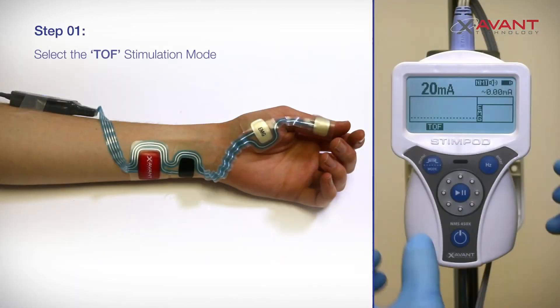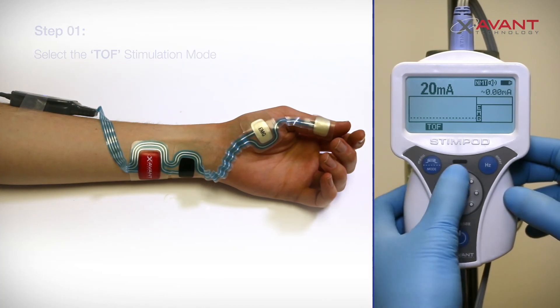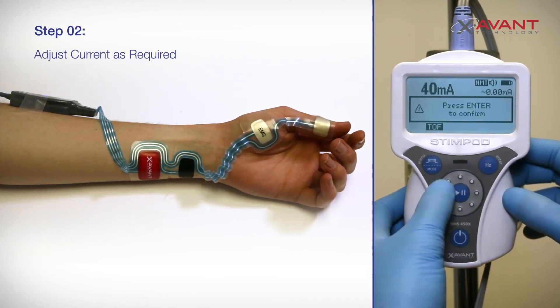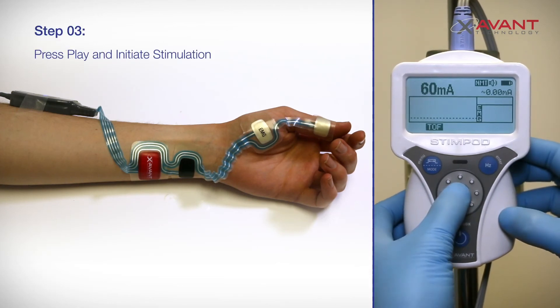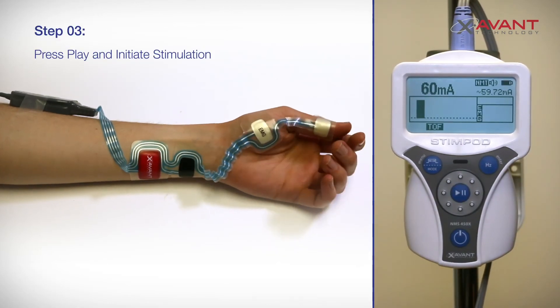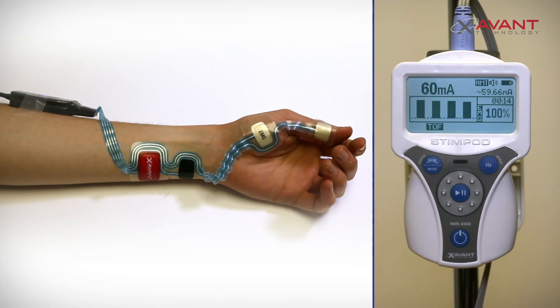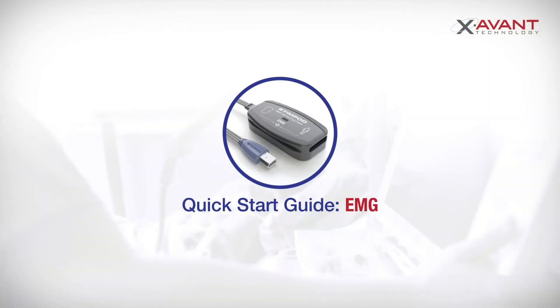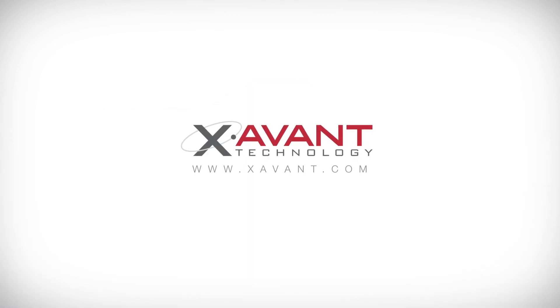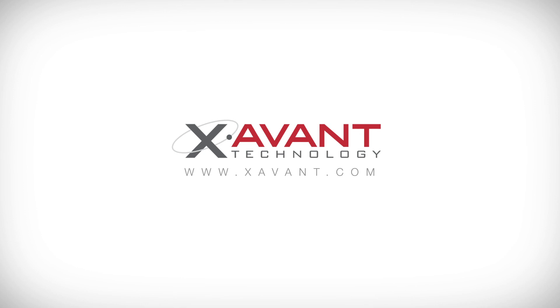Option B: Manual Stimulation — use the mode button to select the TOF mode. Manually adjust the current using the adjustment wheel and press enter to confirm your choice. Press the play button to initiate a single TOF sequence. Press and hold the play button for two seconds to initiate a repeat TOF stimulation function. Thank you for watching our quick start guide for EMG. For further details on our products or NMT monitoring, please visit our website at www.xavant.com.